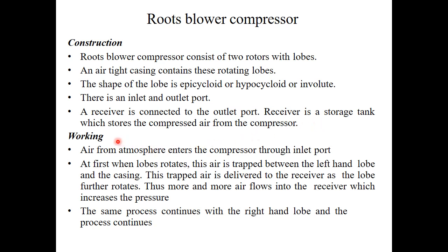Talking about the working, air from the atmosphere enters the compressor through the inlet port. At first, when the lobe rotates, this air is trapped between the left hand lobe and the casing. This trapped air is delivered to the receiver as the lobe further rotates. Thus more and more air flows into the receiver, which increases the pressure. The same process continues with the right hand lobe, and the process continues.